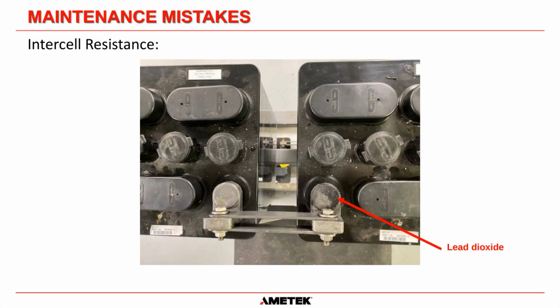Now we're going to go over some maintenance mistakes. One of my pet peeves in maintenance mistakes is intercell resistance. It's a bit difficult to tell in this picture, but this is what the post should look like, a nice gray silvery color. You can see this post here has some lead dioxide on it. That's what this black stuff is. And that usually means that there is a jar cover leak or crack here that is allowing electrolyte to leak up from inside the battery and then up into this post, and it's putting a coating of lead dioxide. And that lead dioxide is very, very hard, and it has a high resistance. So in theory, if the surface of this post to where the intercell connector is connected gets contaminated with lead dioxide and it creeps up and there isn't any grease or anything to prevent that, then it could lead to a high resistance connection.